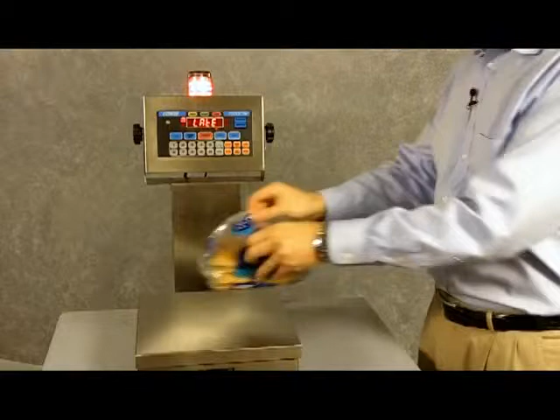And so what happens is that once we see the C on the display, it does not allow the operator to modify the weighment. So if they go ahead and say, okay, I'm going to take a little bit off or add a little bit to the weighment to make sure the data's right, and in the meantime, the scale is still beating the drum saying, hey, you need to take another weighment. So I'll go ahead and take another weighment. We'll see the C show up. If I modify the weight, it does show up on the display, but that C, that's the number that's in the database. So it cannot be modified once it's added to the scale.